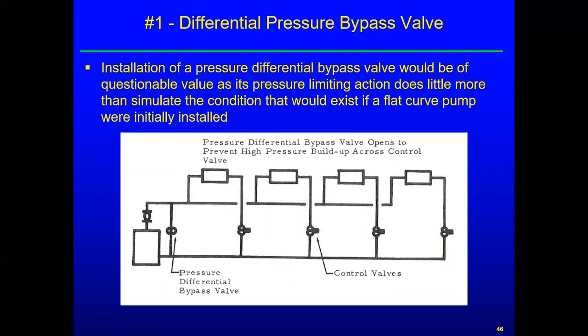Okay, so these are some issues we'll go through. I think there's four of them that'll be discussed here. The first comes up with this. Some designers will sometimes put in a differential pressure bypass valve. This would be for a constant speed pump. And so this slide shows it up along the boiler. You monitor the differential pressure, and if it gets too high, that valve opens, and basically it just lets some flow recirculate. It gives an open flow path if the other four valves are closed or almost closed.